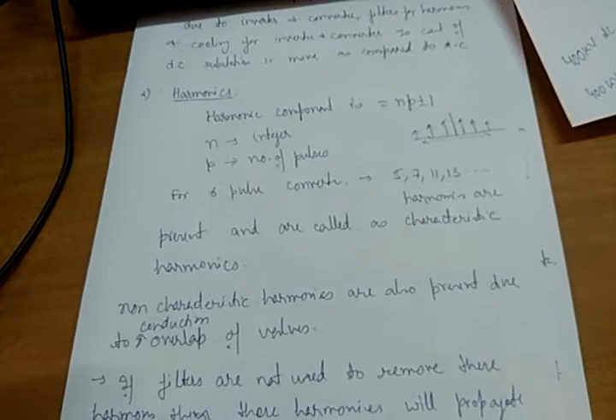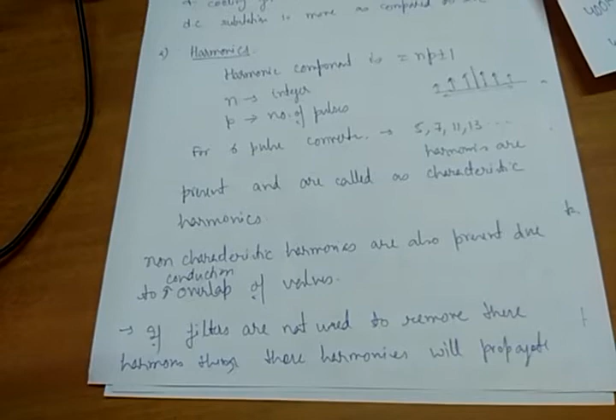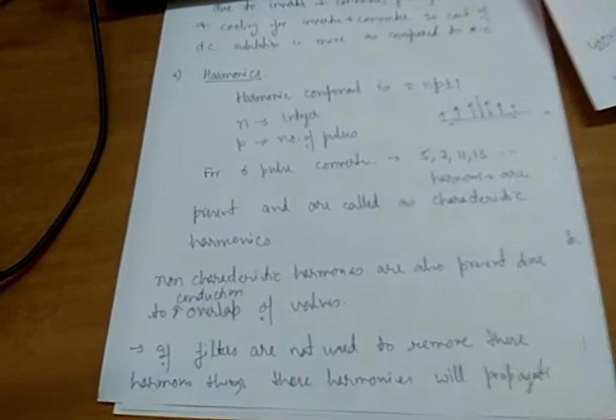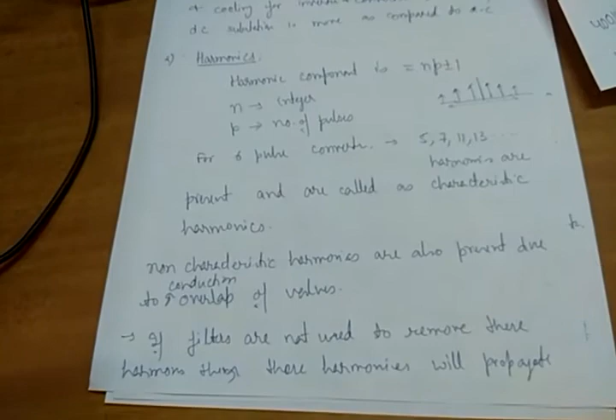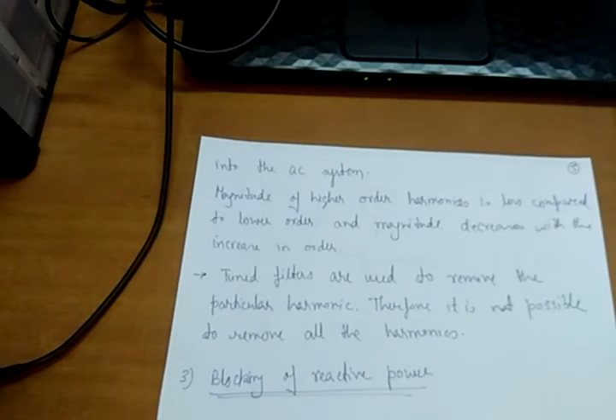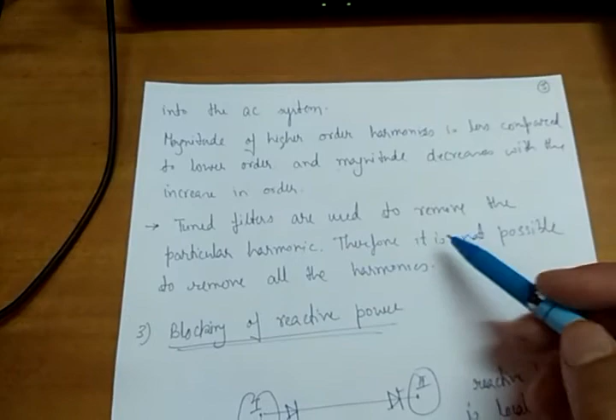So it is not possible to remove all the harmonics from this line. But some of the harmonics which are of higher magnitude need to be removed, because if they are not removed, they will propagate into our AC system and cause troubles there. To avoid that, we need to remove the higher magnitude harmonics. Tuned filters are used to remove a particular harmonic. Therefore, it is not possible to remove all the harmonics.